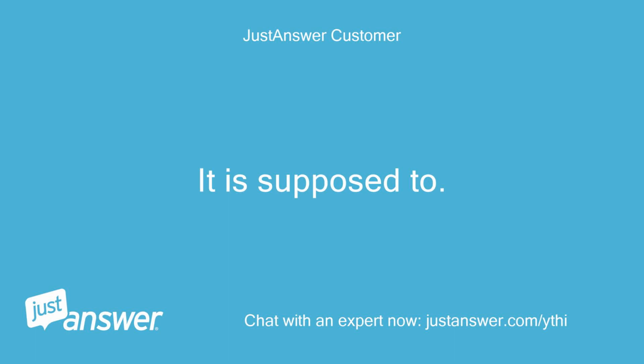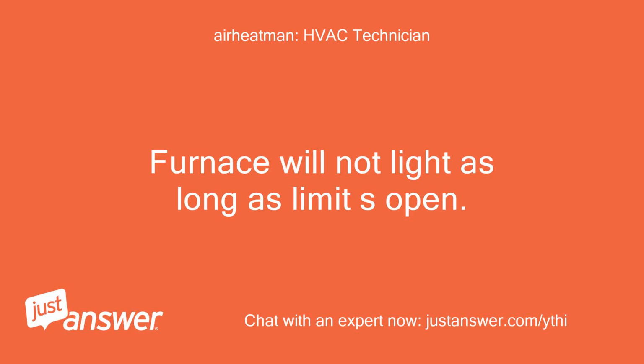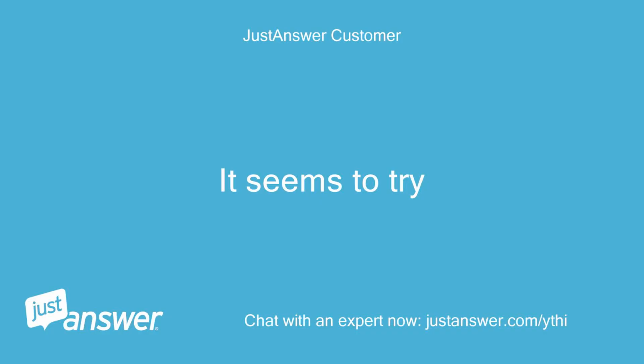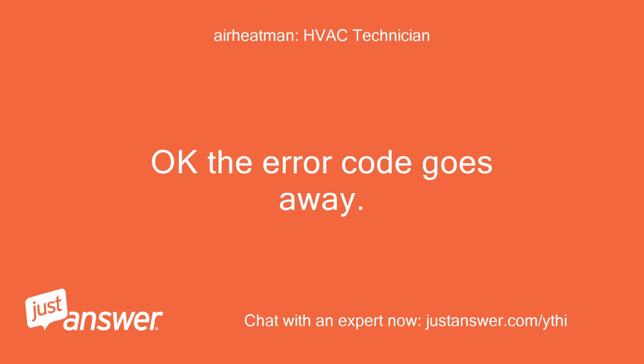It is supposed to. Everything seems to be working but no gas coming in or pilot on. Furnace will not light as long as limit is open. Does it reset if you turn power off and back on? It seems to try. The thermostat had to be replaced. It appears that perhaps it shut off when that went out. Now won't restart the pilot? Okay, the error code goes away.